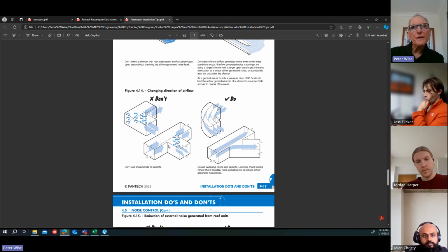Changing direction of airflow. Recommendations: don't use square bends without vanes. Try and use vanes, or use radius bends wherever you can. It would be my advice. That's what we always tried to do. Sometimes you're restricted for space and you have to use a square bend, but put some splitters in the square bend to get the air to flow smoothly around the bend. If you've got a branch, do the best you can to get a smooth takeoff for the branch. We don't do these Y-shaped branches very often. We normally have a shoe to reduce the velocity as it enters the bend. And that helps to reduce noise.